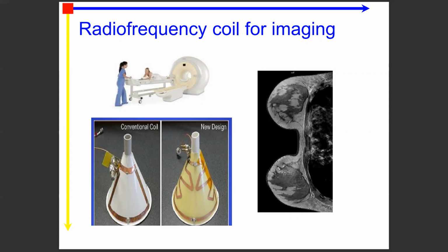Imagine you have to also design that and optimize it. So this transmit receive coil, this one here, is a transceiver, so it does both functions, not separately. It does both transmission and reception. It is designed, as you can see, using stream functions or some sort of sophisticated maths, having an objective function optimized using the conjugate gradient method or some sort of Newton's method or similar.